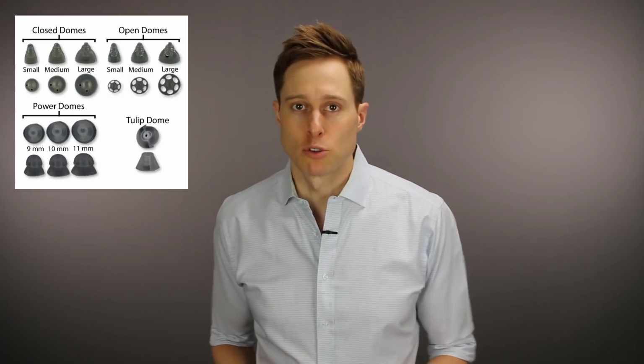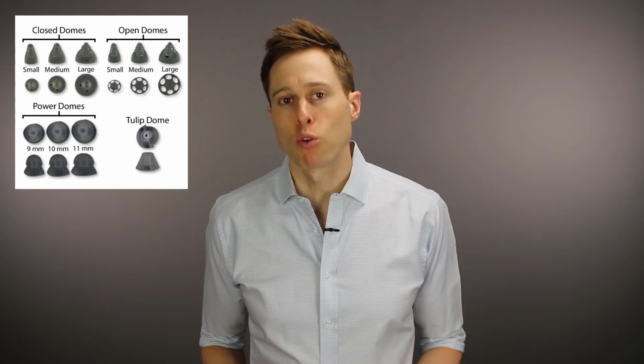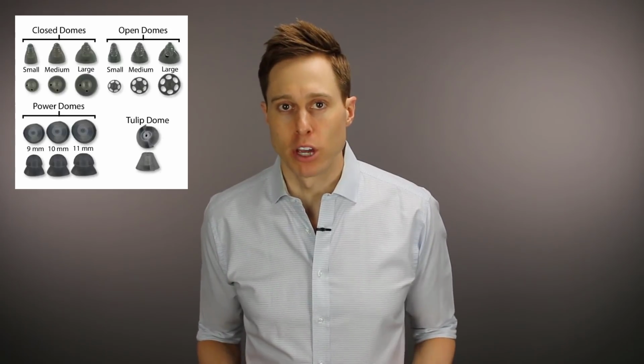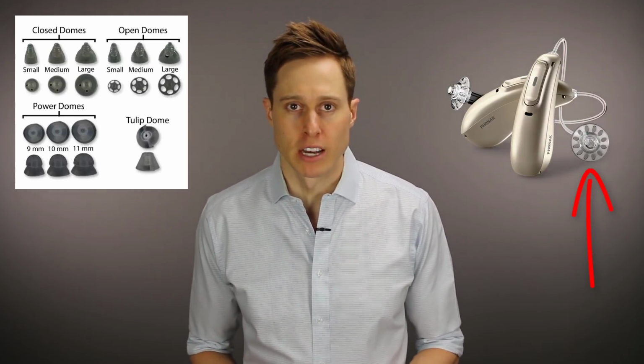The second tip is to try a different rubber dome. I would bet that there are a lot of individuals out there walking around with the wrong type or wrong size of dome on the end of their hearing aids, which is the portion that goes inside of your ear canal. A poorly fit dome can lead to issues of migration, which is where the device will work its way outside of your ear, which will reduce the amount of amplification that you're receiving, not to mention leave you exposed to problems with feedback or that whistling sound that you hear when a hearing aid isn't fit appropriately. Using a different size or style of dome can have a major impact on the way that a hearing care professional can program your devices. It is a really simple fix, but it's something that's critical if you want to hear the best with your hearing aids.